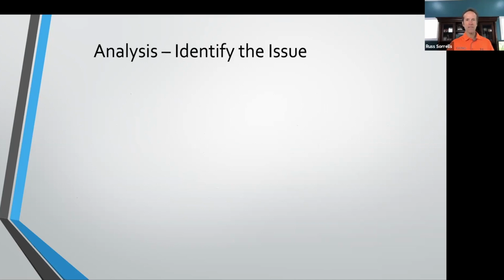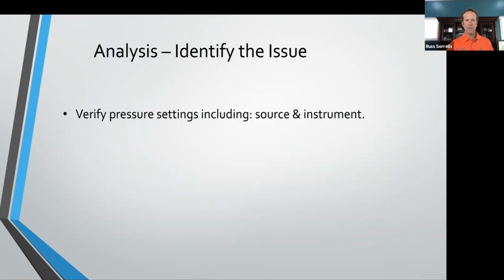For sure. All right. So continuing to discuss here the identifying the issues. We want to verify the pressure settings of the instrumentation, as well as the pressure source. What I mean by that is if your test pressure is 80 psi, your regulator setting on your instrument will need to obviously be set to 80 psi.